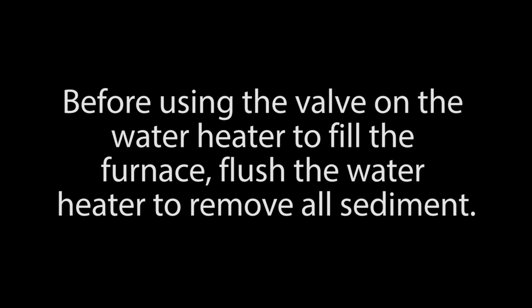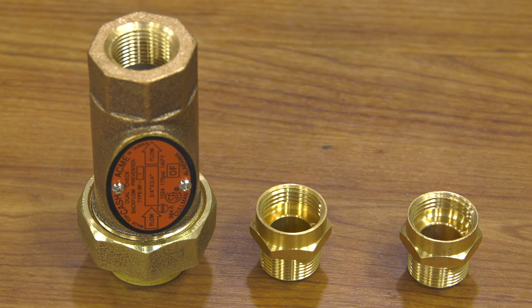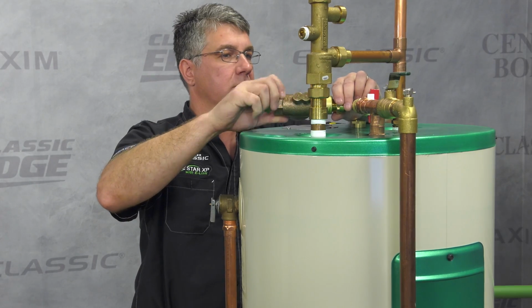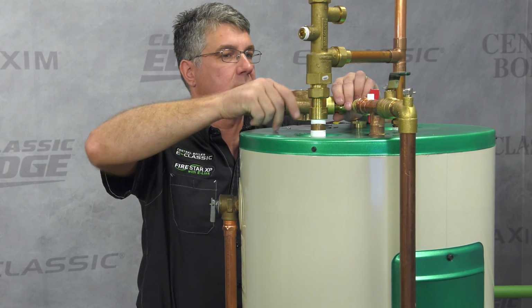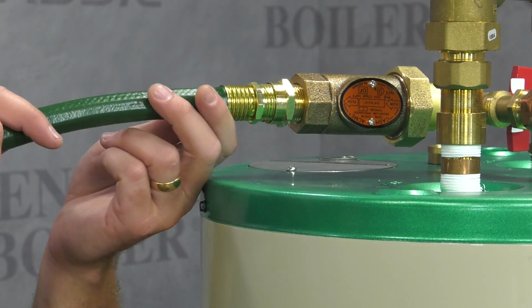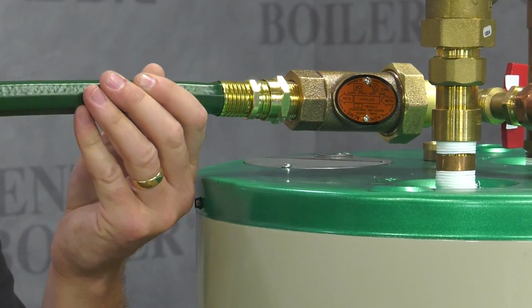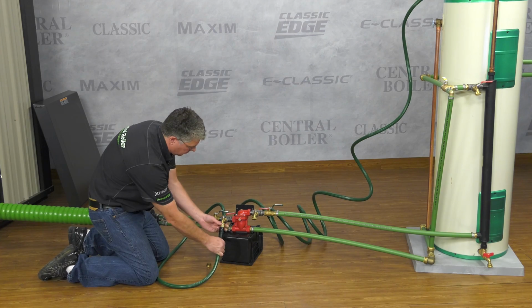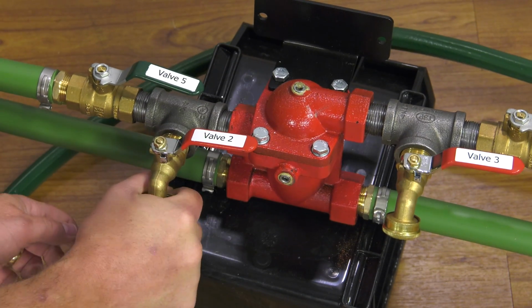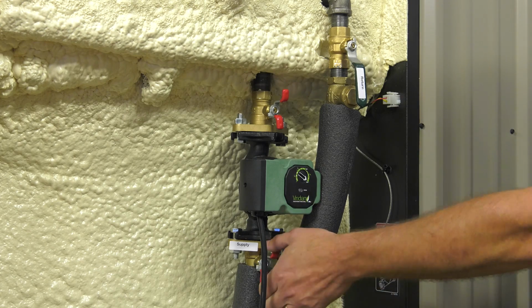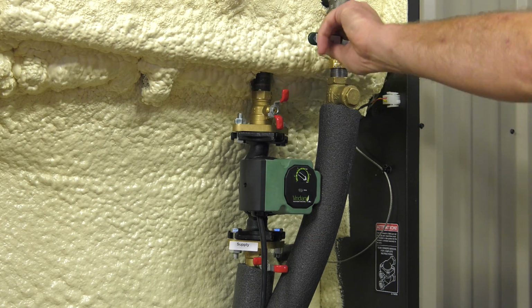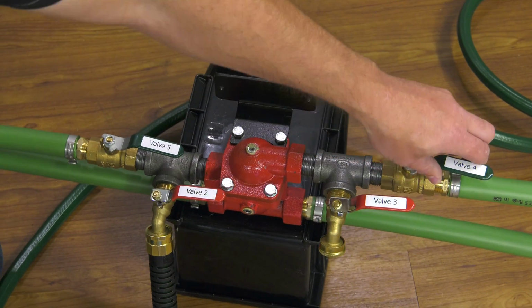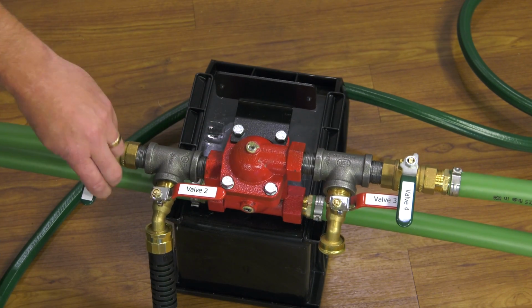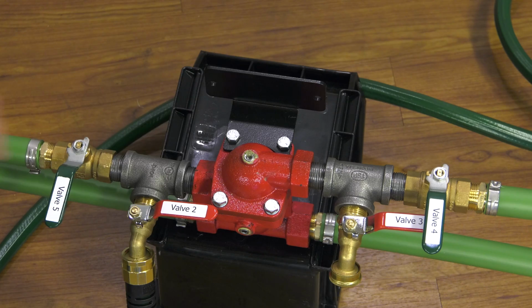Before using the valve on the water heater to fill the furnace, flush the water heater to remove all sediment. Use a backflow prevention valve with two 3/4 inch female hose to male pipe adapters on the water heater. Connect the male end of a garden hose to valve 1. Connect the female end of the garden hose to valve 2. Close the valves on the hot supply and return lines of the outdoor furnace. Close valves 4 and 5. Open valves 1 and 2.